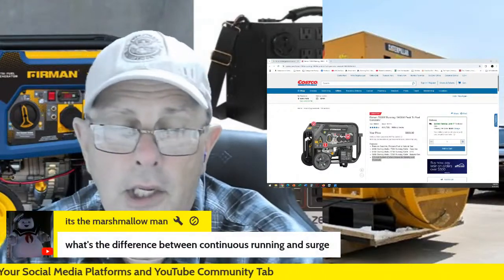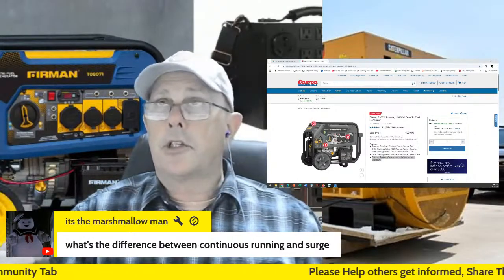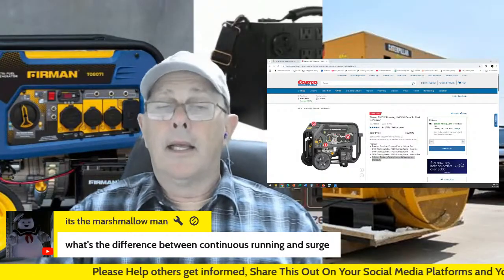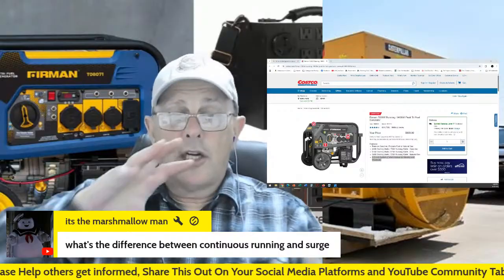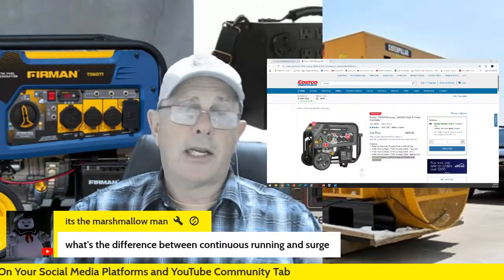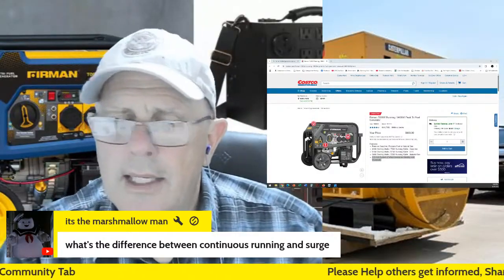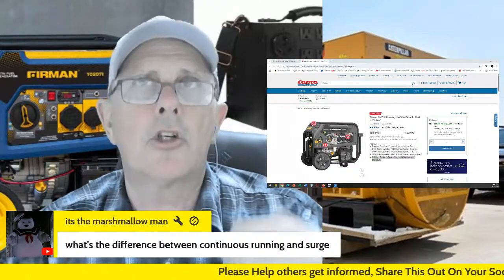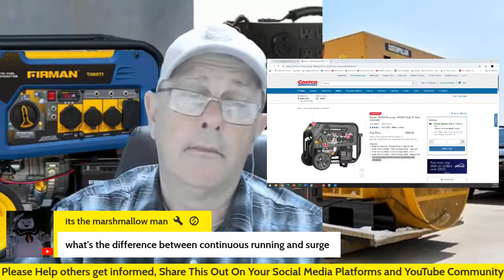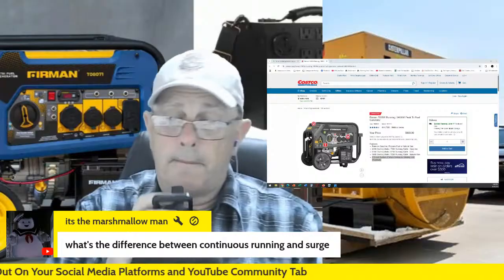And what's the difference between continuous and surge? Okay, so you plug in your refrigerator. Your refrigerator draws continuously 750 watts. But to start up, it may start that motor and compressor going. It may draw 1100 watts for the first 5 seconds. So that's what the surge is for when you got electrical motors starting up. Hair dryer kicks on, that first little bit, it's going to surge a little bit more than when it's running.